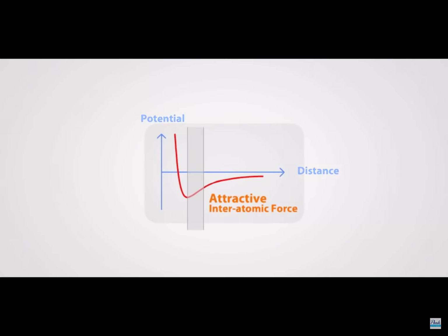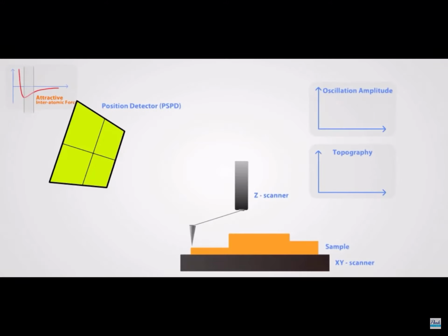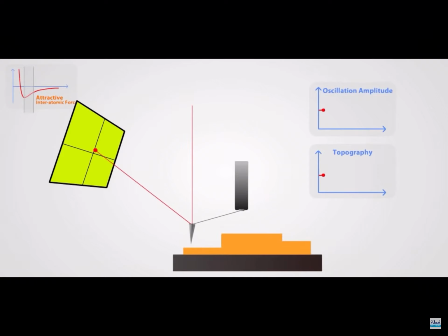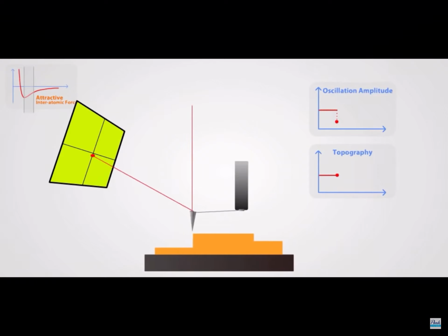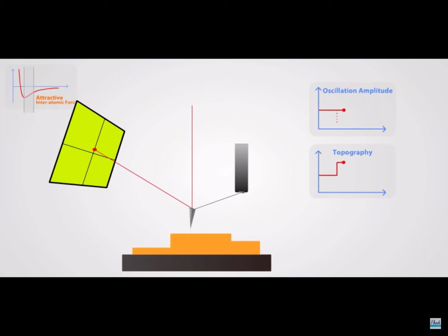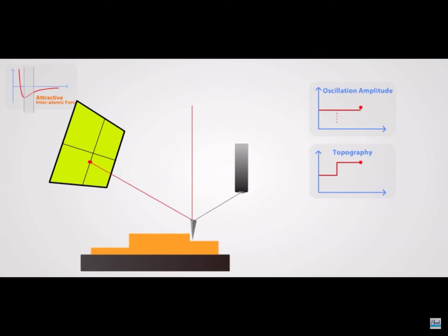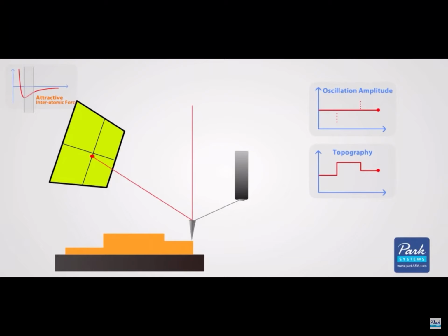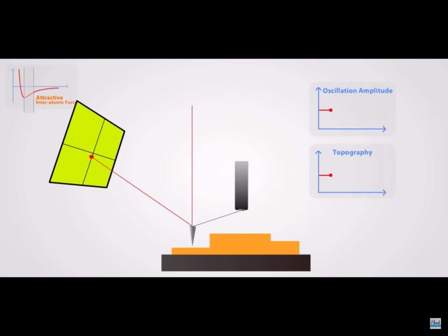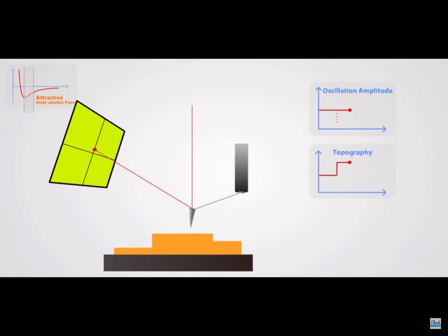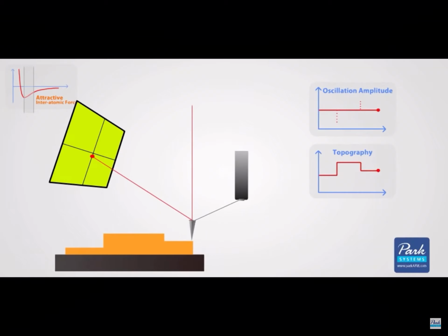In non-contact AFM, the cantilever oscillates just above the surface while it scans, but the tip does not touch the surface. A precise high-speed feedback loop is used to keep the cantilever tip from crashing into the surface, thus retaining tip sharpness and leaving the surface untouched. As the tip approaches the surface, interactions between the tip and the surface cause the oscillation amplitude of the cantilever to decrease. The feedback loop corrects for these amplitude deviations and constructs an image of the surface topography.